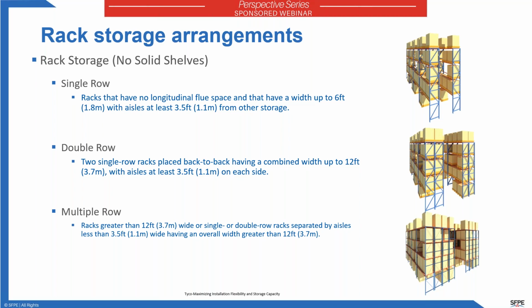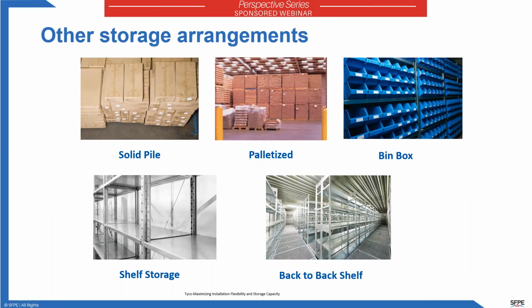And a lot of my presentation will focus on rack storage arrangements and the effect that sprinklers will have on how many pallets can be stored on the racks. I actually talk about how many racks you can fit into a space, and therefore how many pallets you're able to store. Obviously, there are different storage arrangements that are also in warehouses. I mentioned solid piled, things stacked right on top of each other. Palletized, which is pallets of goods stacked on one another. Bin box storage arrangements. Shelf storage. Racks are not shelves. Shelves get their own definition in the fire protection standards. So you have standard short shelf storage as well as back-to-back shelf storage. So as with commodity selection, it's important to understand the type of storage arrangement, as the combination of commodity as well as storage arrangement will dictate the type of fire protection that's required.